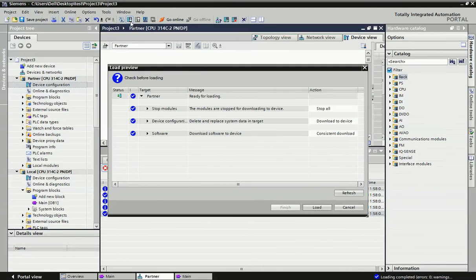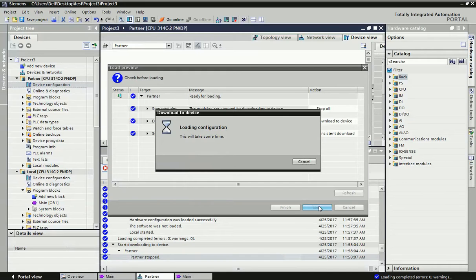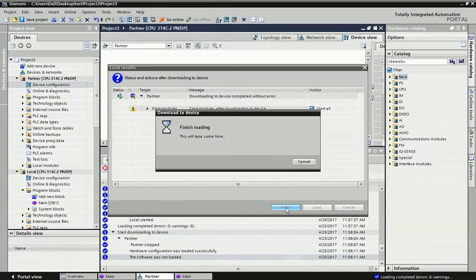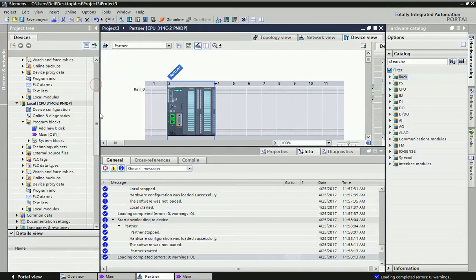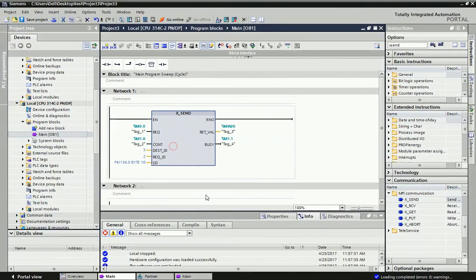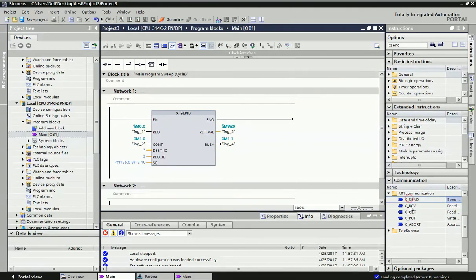After downloading the hardware configuration for both PLCs, we take programming blocks for MPI communication. Going into the local PLC, from the instruction options we open the communication folder, which contains MPI communication functions. From MPI we have two blocks — XSEND and XRECEIVE — for communication between two PLCs using PROFIBUS cable and MPI.